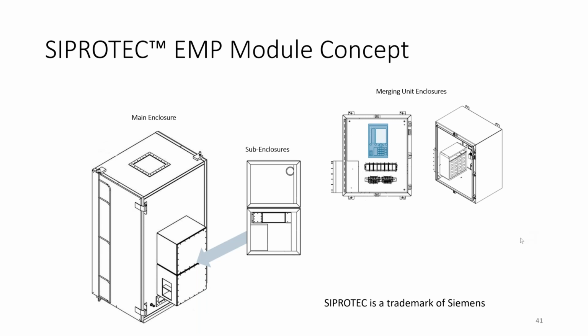On the side of that are two sub-enclosures, which allow us to bring filtered power in and take filtered power out to the merging units that you see on the right-hand side. In between those two enclosures is the fiber optic connection. And inside the merging unit enclosure is where we house the surge suppression that's been referenced today, which allows us to protect for the coupled energy that the equipment might be exposed to through the instrument transformers. That really reduces the number of surge suppression devices that we need, and it also places them as close to the beginning of the circuit as possible. Next slide, please.